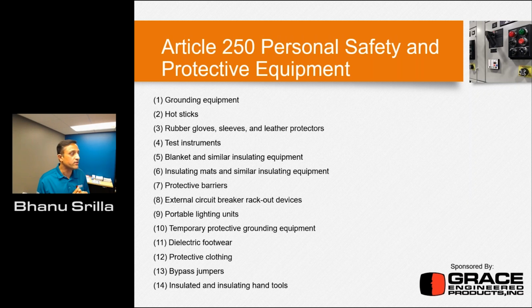So Article 250 is a huge list, because this is one of the major foundations of electrical safety, because PPE and the protective equipment and personal safety are very, very critical. I'm highlighting these 14 things here: grounding equipment, hot sticks, because these are all used. If you take electrical safety in context, these are the things that electrically qualified workers will use on a day in, day out basis. So they bring a predominant focus on this specific area, because there is a huge need for people to make sure that things that will protect an employee in case of a hazard are properly maintained and also tested on a regular basis to make sure that there are no deficiencies in that effect.